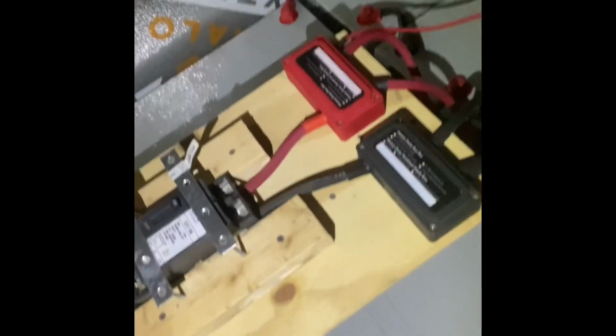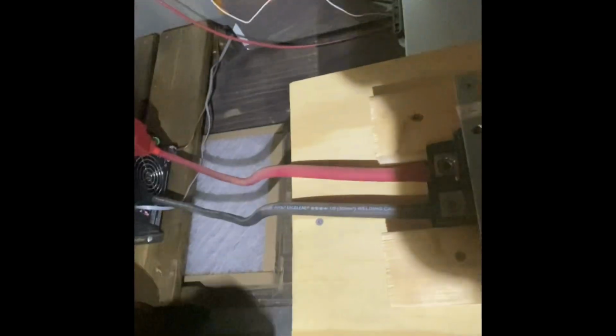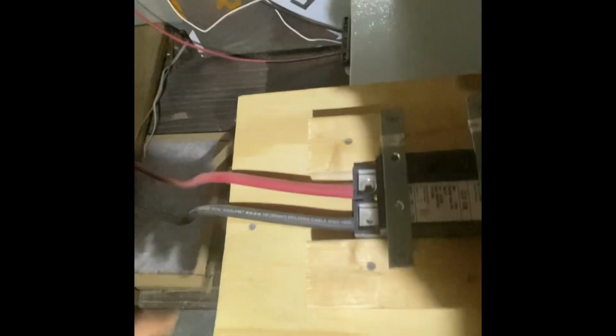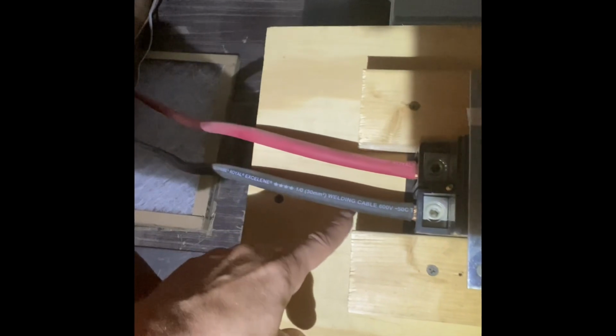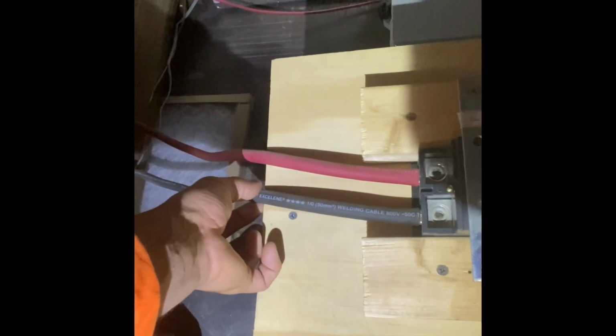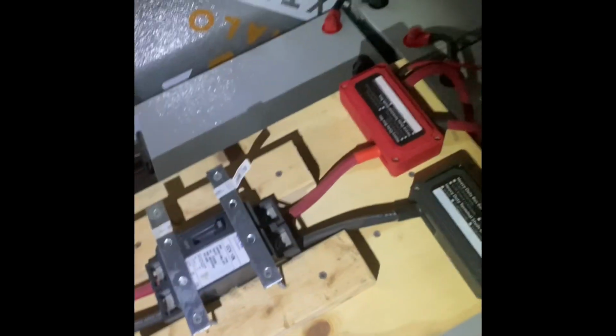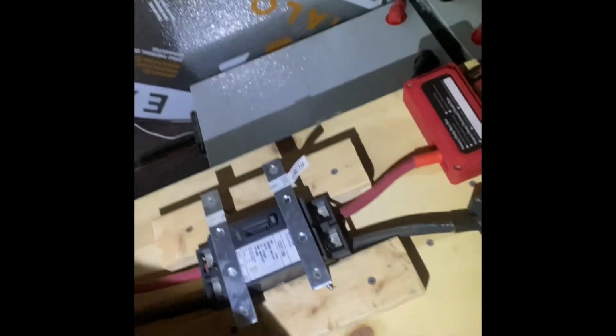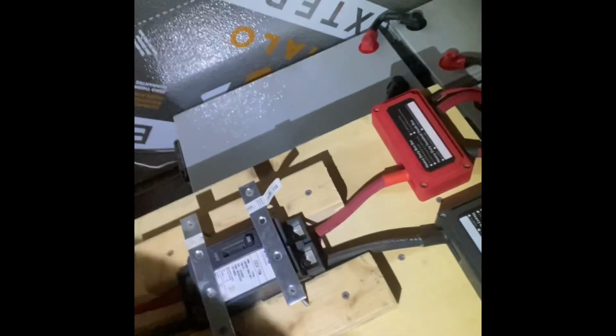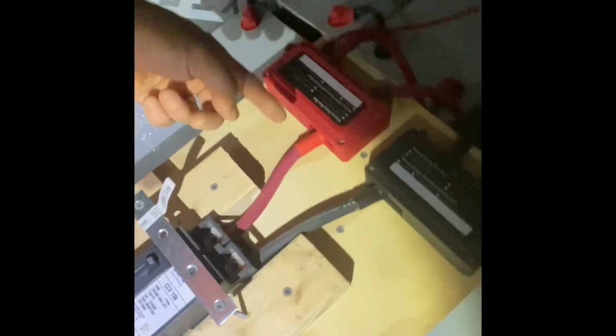So this is 1/0 wire, you can also find this off Amazon. This is Southwire, the brand name. I like this wire because it's a welding cable, so if you're looking for this type of equipment, look for a welding cable or welding wire, because this is like a soft rubber, very pliable and bendable. There's some 1/0 and 4/0 wire that has a really rigid coating and you can't work with it too well, you can't bend it into tight corners. This is very pliable, so I do recommend a welding cable.